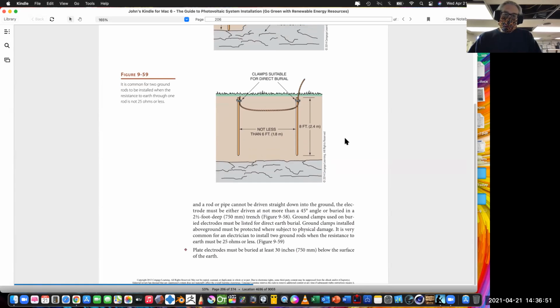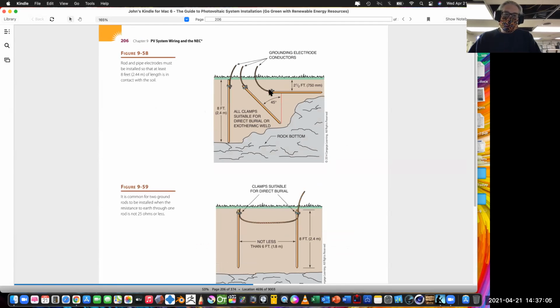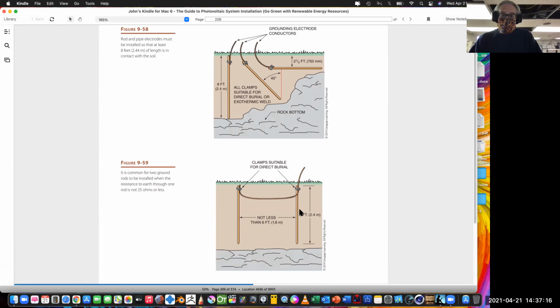So what we end up with is the idea that we need to make sure, in the most simple sense, that our ground rod is measuring 25 ohms or less. If it's not measuring 25 ohms or less, then we have to do something different. Generally add another ground rod in a different place and connect them together, or move it somewhere else, because you're probably in rocky or clay-like, sand-like material instead of good dirt.